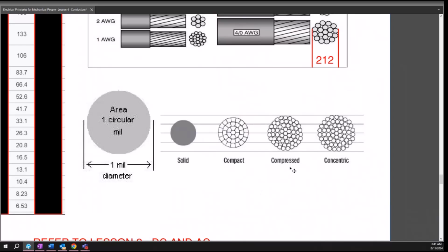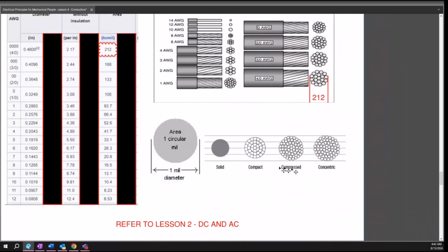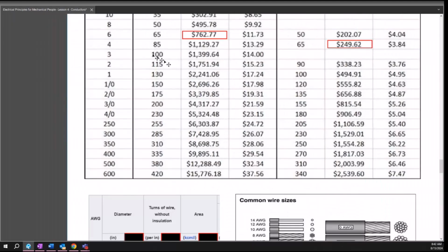Now if you need a smaller physical size but still the same ampacity, you can get either compressed or compact. Most of the time I see compact on medium voltage stuff, and compressed more on low voltage stuff, like 600 volts and below. If you hear that, just think smaller physical wire but still the same ampacity as whatever the number is—it has not reduced ampacity, it's just taking up all the extra little space in there.